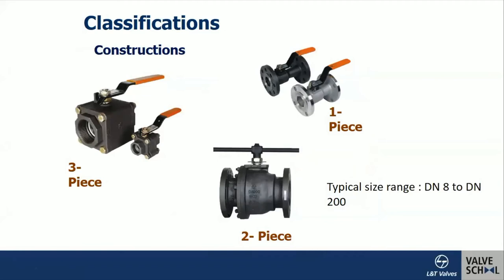We will look at the classification of ball valves based on construction. There is a three-piece construction, which has one body and two connectors bolted together. Three-piece construction is very good for inline maintenance — you need not remove the valve from the line. Of course you have to isolate the line, but you can remove three bolts, swing it like a fulcrum, and change all internals: ball, seat, body seals, and so on.